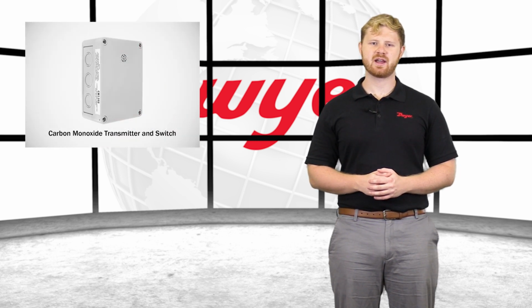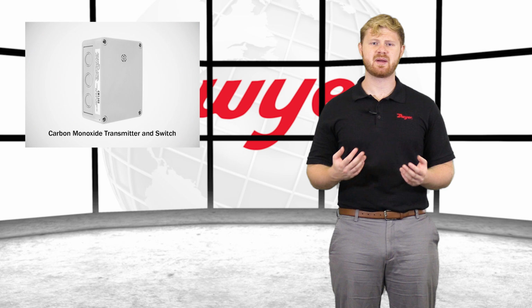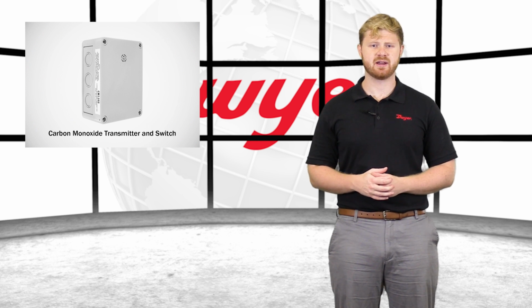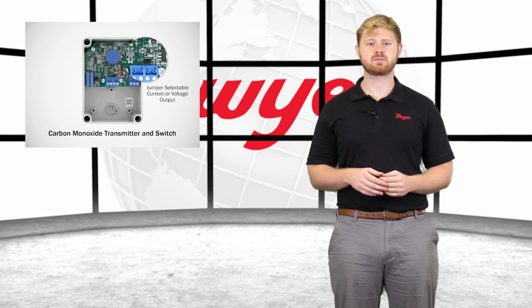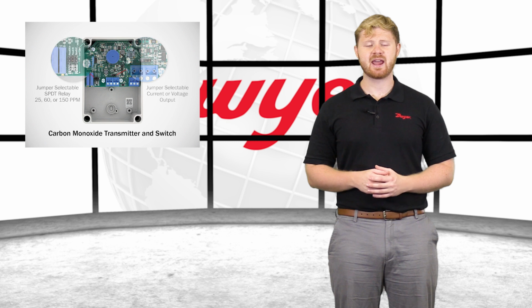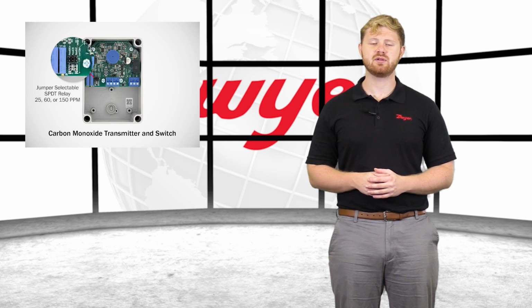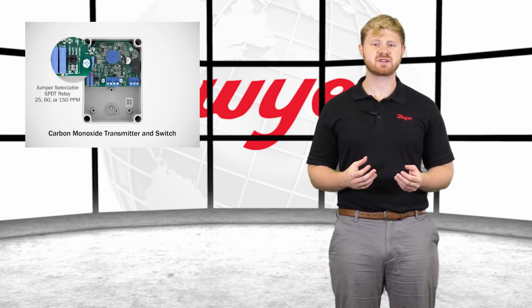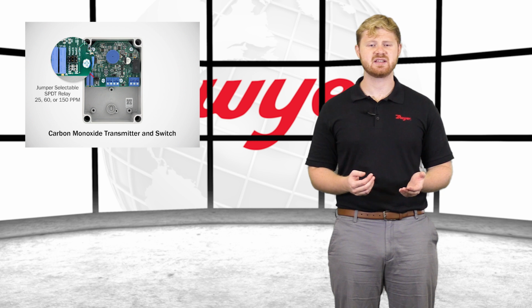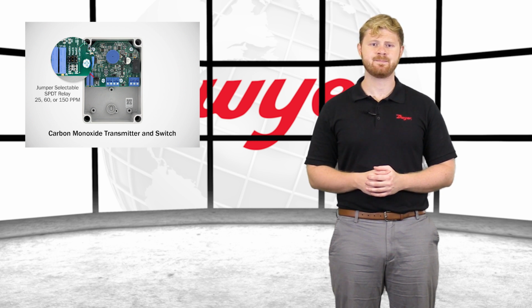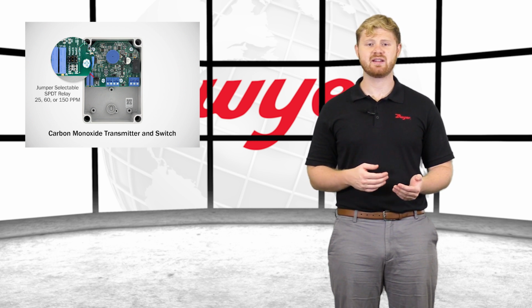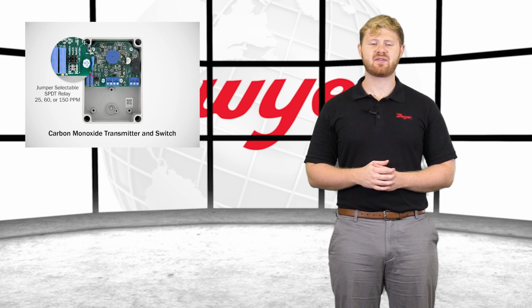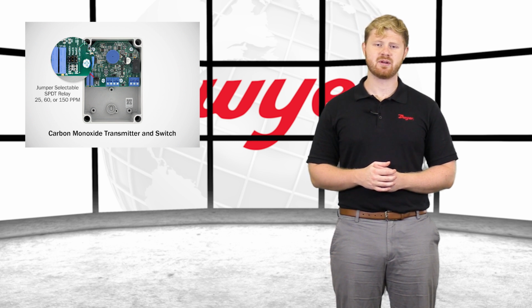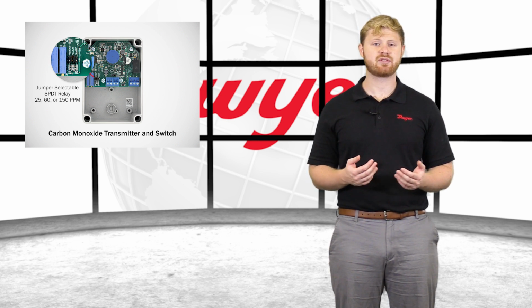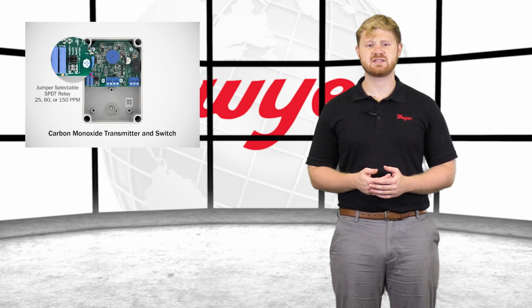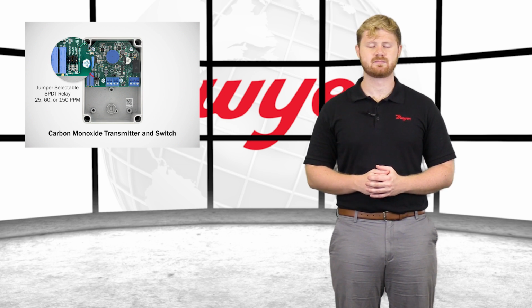The CMS300 can be easily customized depending on the type of alarm needed for a scenario. In addition to the field selectable current or voltage output, an integral SPDT relay can be used for alarm conditions and is jumper selectable to 25, 60, or 150 ppm. This implementation of a relay and transmitter allows for the device to alarm the building management system while providing a relay that can be paired with local alarms, such as visual lights or audible buzzers.